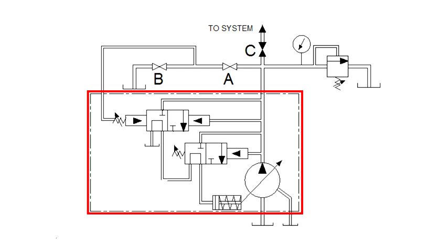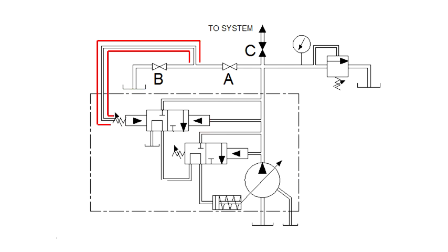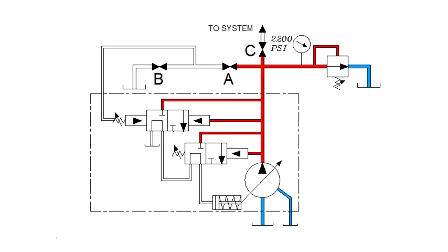The portion inside the dotted lines represents the pump, its pressure compensator valve, and its load sensing valve. A small line coming from the spring represents the load sensing pilot line. The system should be deadheaded downstream of the relief valve, with a gauge mounted to read pressure.